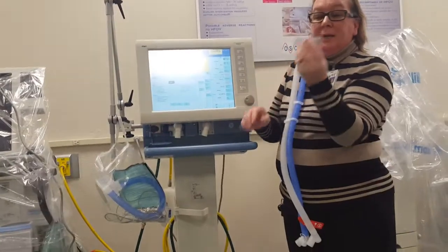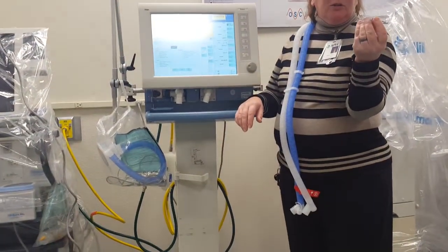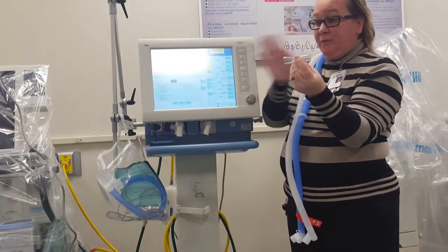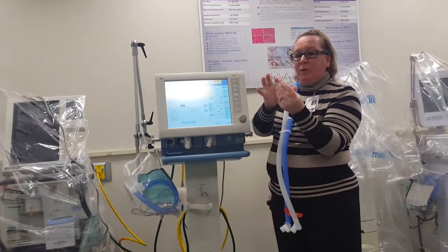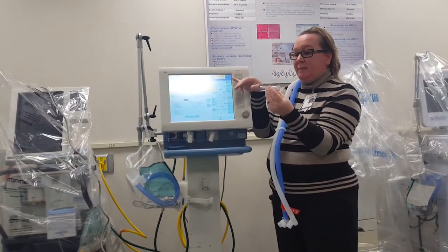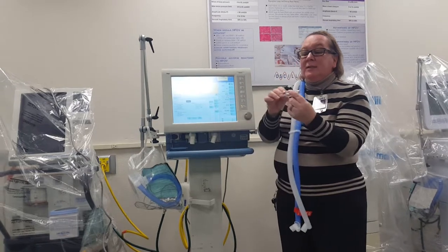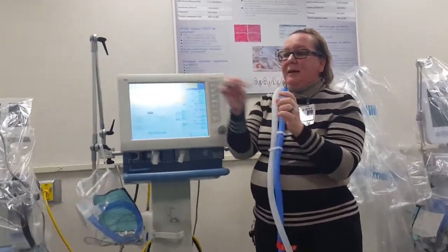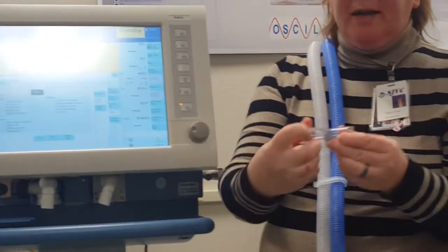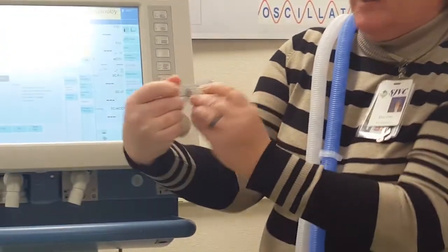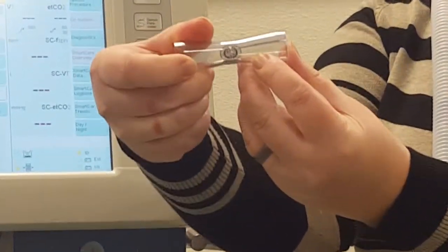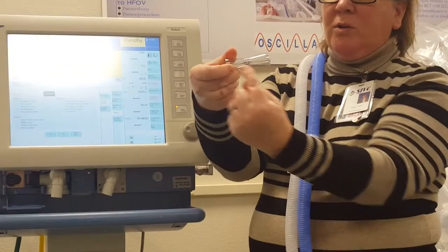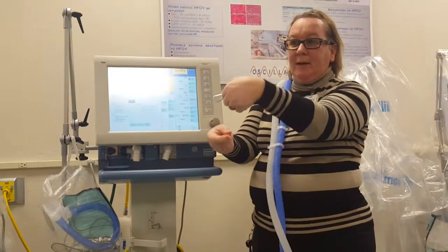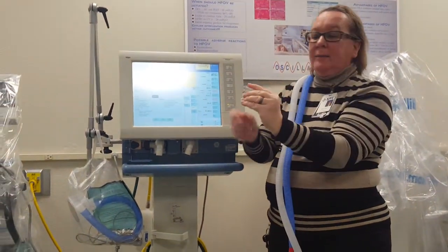I really should tell you this stuff before we get going any further. This little piece here is a flow sensor where it's going to sense all the flow. It calibrates it, and this is actually where the flow readouts are taken on the machine. It has little filaments inside, and it has the word DRAGER, and it says Spirolog on it. When you're putting it in, you need to make sure that the words are right side up, not upside down, because that's how you know it's in the right way.